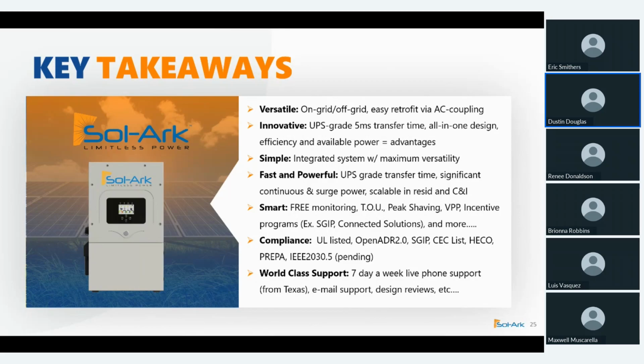So if you have another power source like a turbine or a fuel cell, there are some requirements — this question came up in the chat earlier too, about how AC coupling works, at least within the 30K. It's very similar to the 15 and the 12. We have that gen input for the AC coupled power source, whether that's a fuel cell, micro, or wind turbine. It could be another grid source or another inverter. That's not a problem, since we don't communicate with those devices — as long as that device adheres to UL 1741, either SA or SB, it has the necessary requirements to adhere to frequency shift. That's where it just depends.